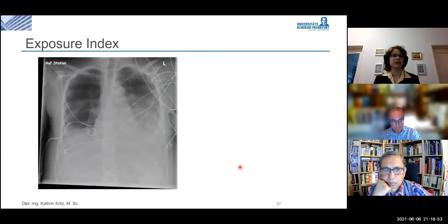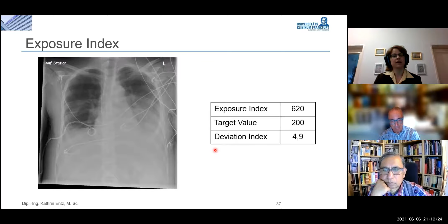On the other hand, we have another example from a different system that you can see here. And you would say the image quality is not bad, but if you look again at your exposure index and the deviation index, you suddenly see that the deviation index is much higher than the 0 we should have. So this patient was overexposed. Because you cannot see it in this image, you should always look at the deviation index and see what you can do if it is necessary to adjust the parameters.